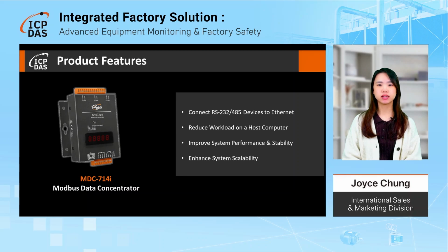Additionally, the MDC700 series enhances system scalability, making it a reliable choice for expanding and managing large-scale operations. In this case, it collects Modbus RTU data from the ISN 800 series IR temperature sensing modules and alarm sirens. The data is then sent to the host computer using Modbus TCP protocol.